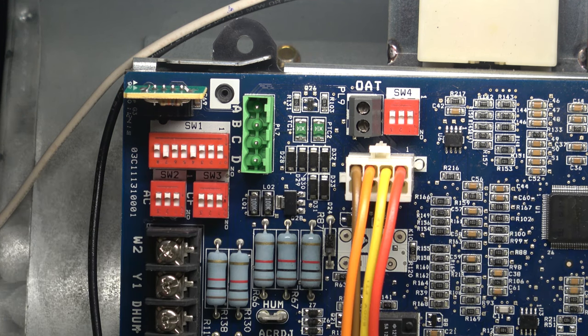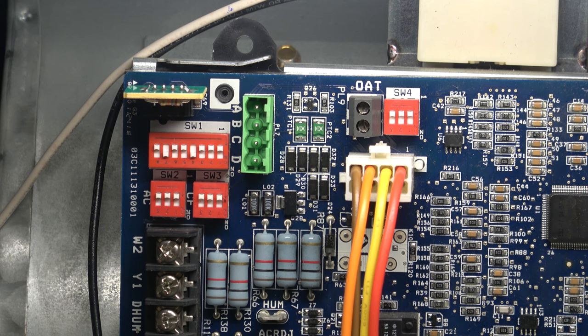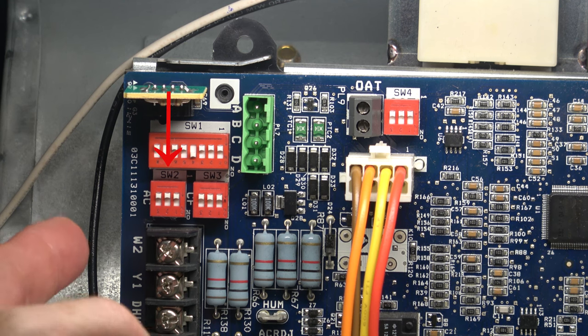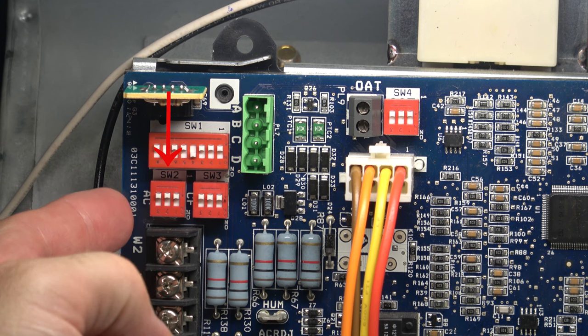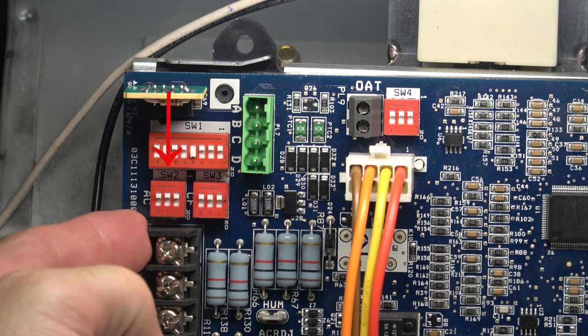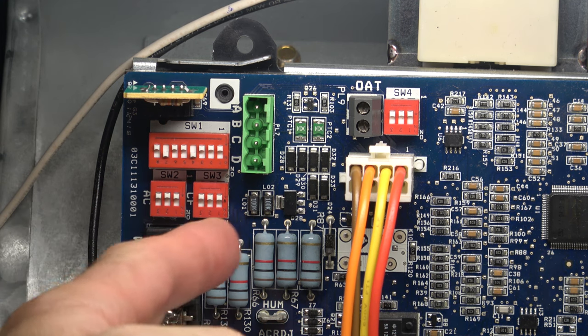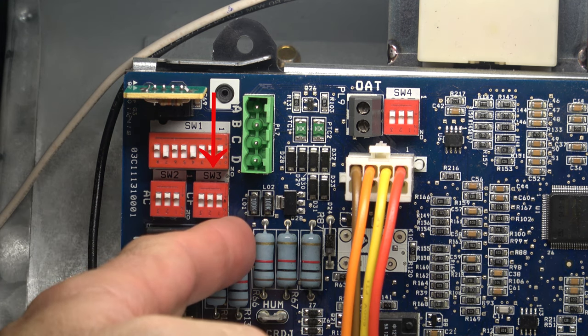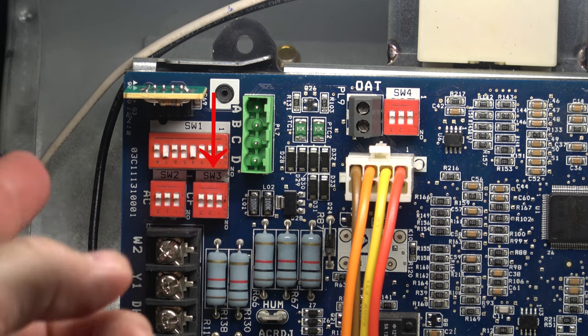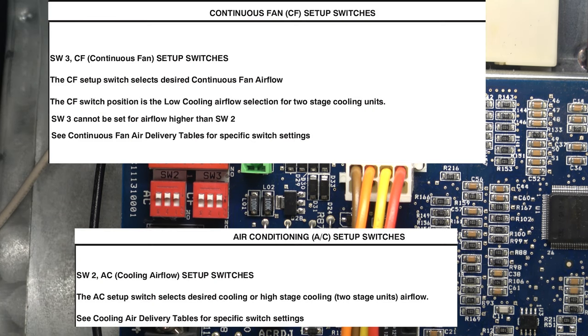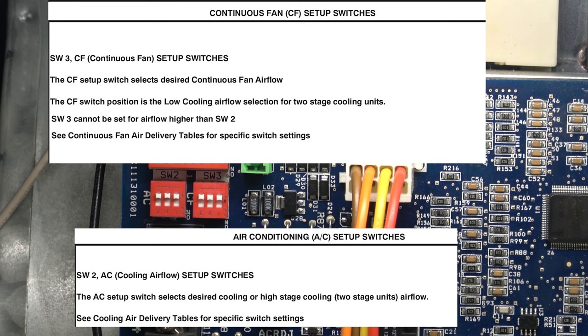The remaining setup switches are SW2 and SW3. SW2 is located on the outside of the board, and SW3 is on the inside of SW2. Those are strictly for airflow. SW2 is your AC airflow, and SW3 is your circulating fan airflow. Those adjustments are made per the charts provided by the factory that we are showing now.